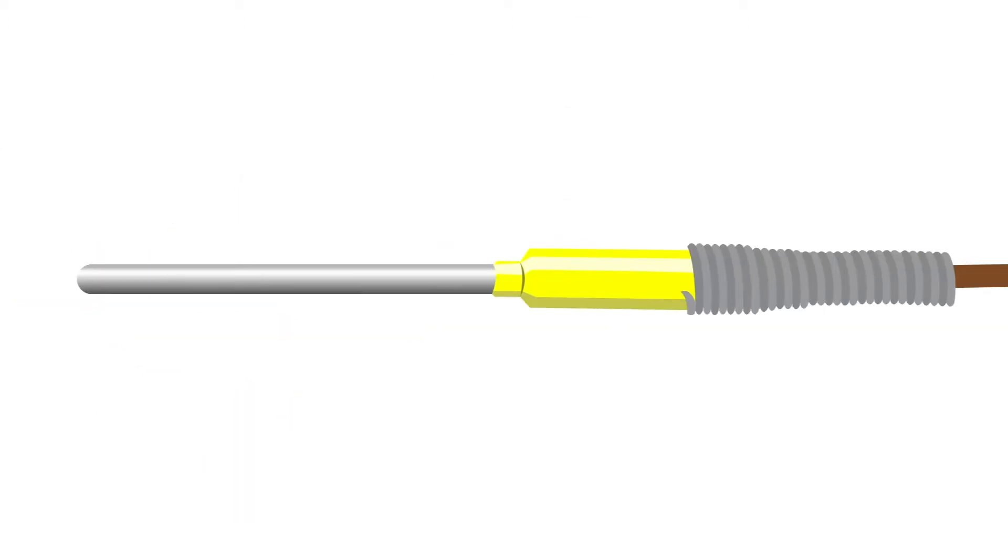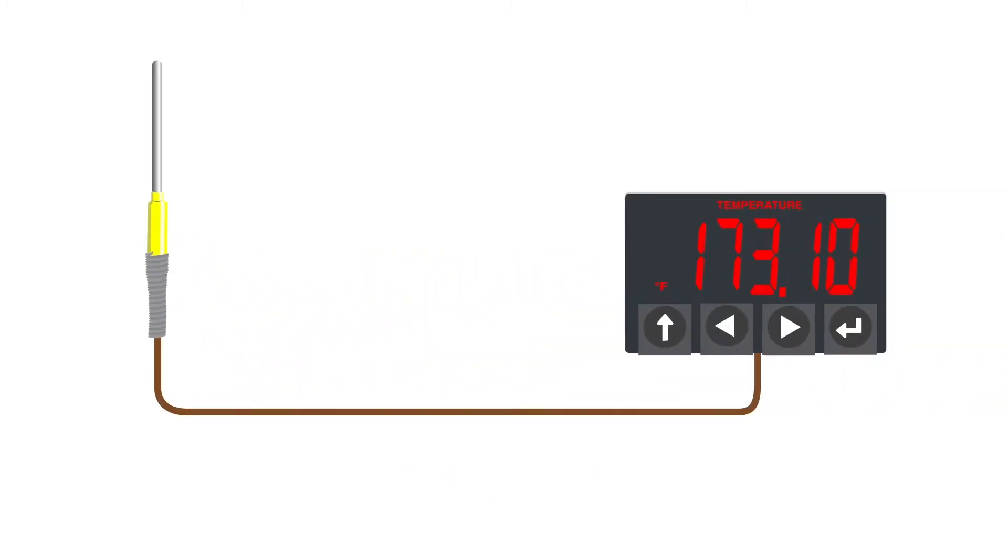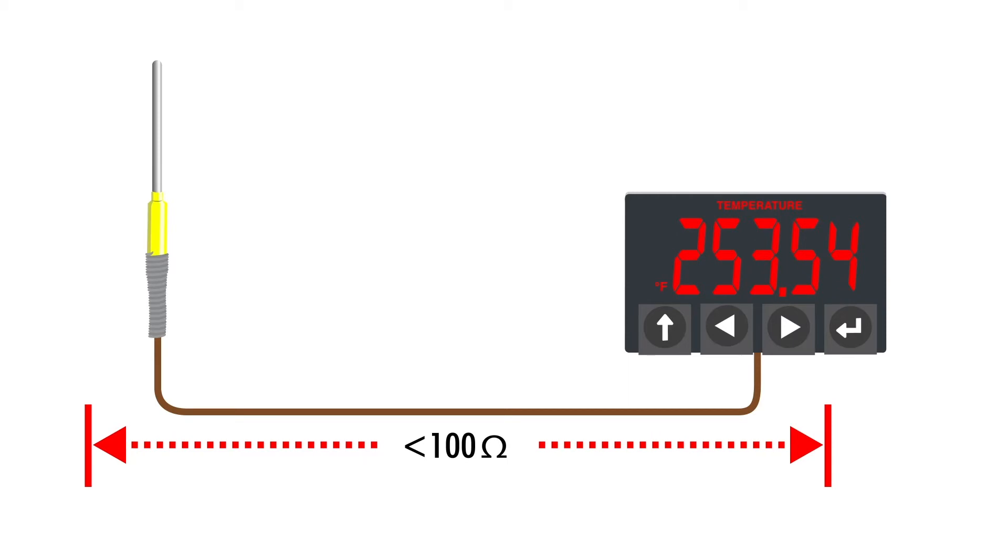First, let's look at resistance. When using a thermocouple, as a general rule the total resistance of the sensor and the wire from the sensor to the indicator should never exceed 100 ohms.